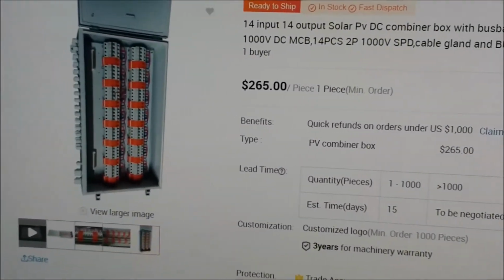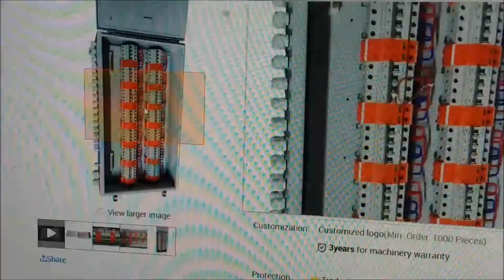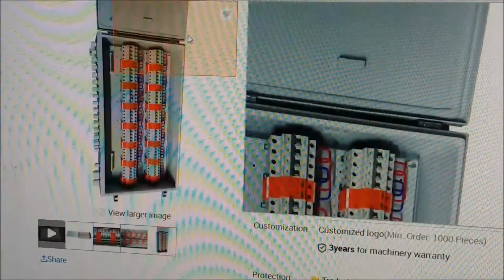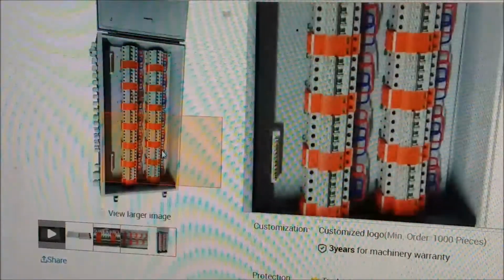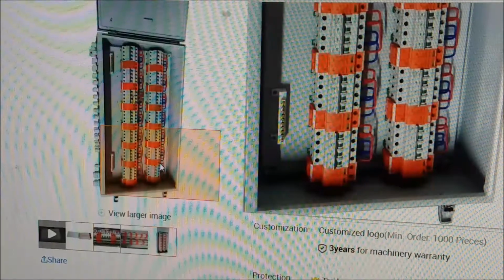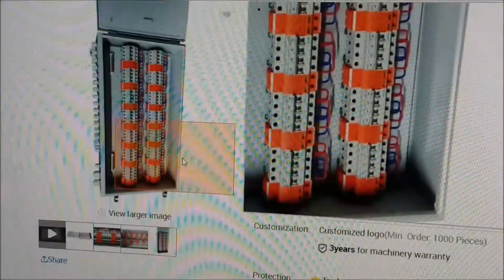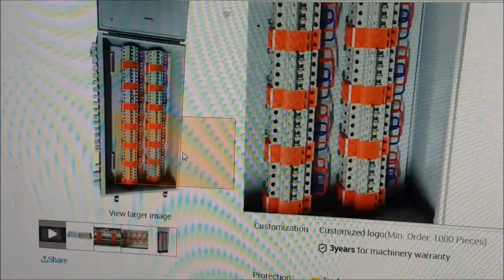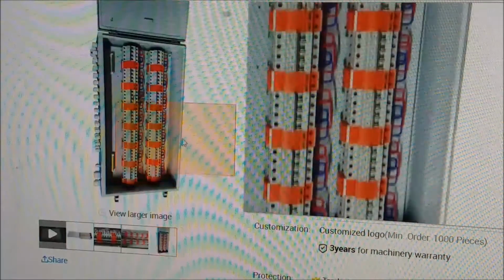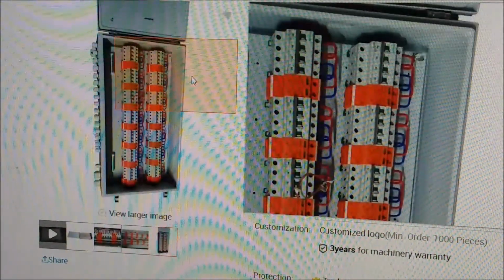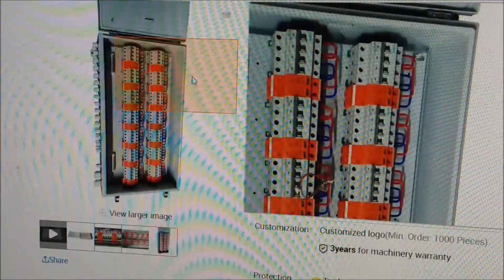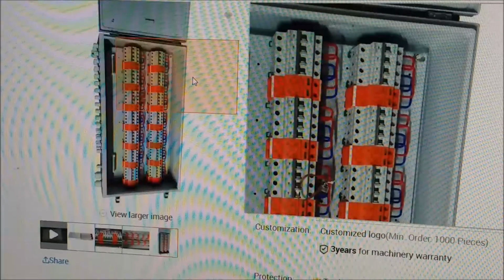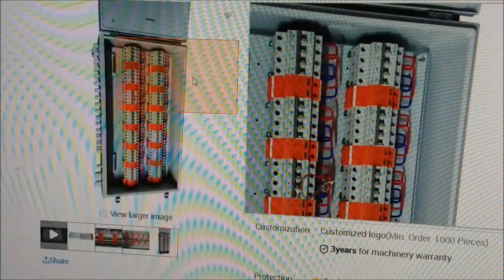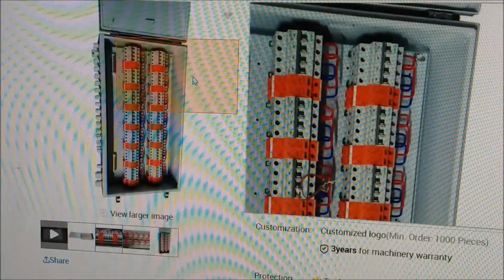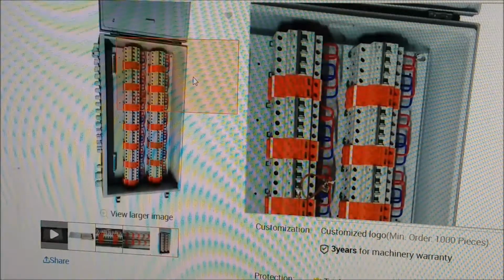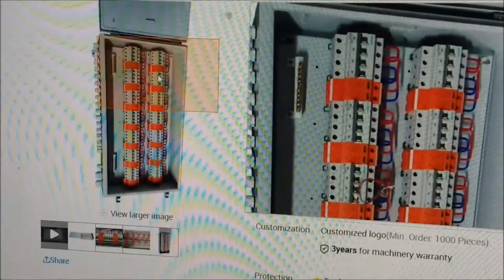Now, obviously, the 14 circuits, and this is a galvanized painted box here. Gasketed lid. Also, a nice thing about these is this panel. If you look on the right-hand side between the sidewall and the bottom, you'll see the edge of a piece of sheet metal, and the top right corner of that piece of sheet metal is a standoff and a nut. So you've got a welded stud in the bottom of the box, and that's called a back plate. So all the screws and stuff that hold all this stuff down don't penetrate the box to the outside. That's another thing you want to look for in a combiner box, because otherwise all the screws would just be water entry points.